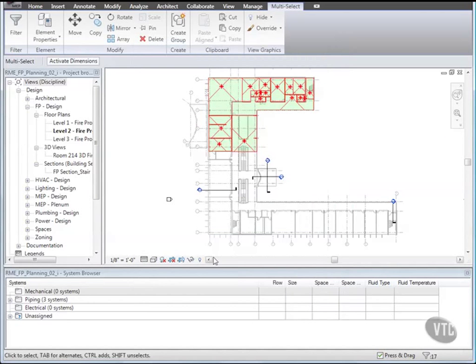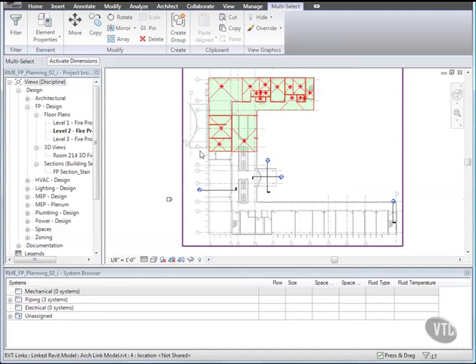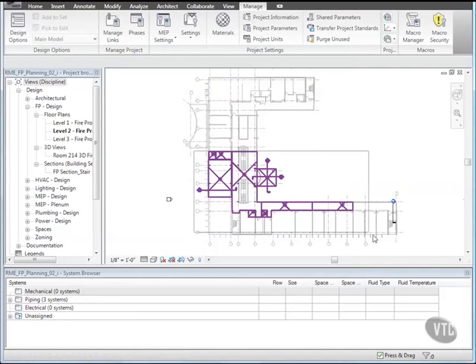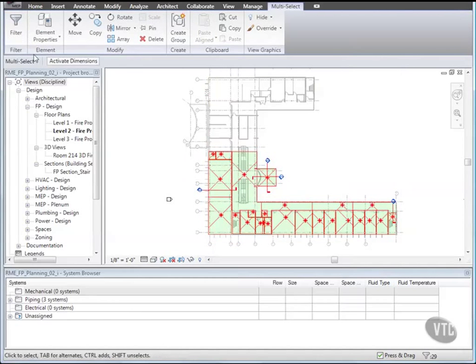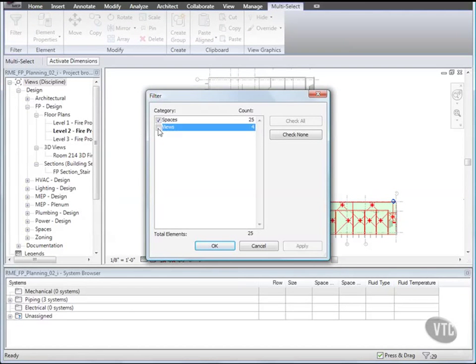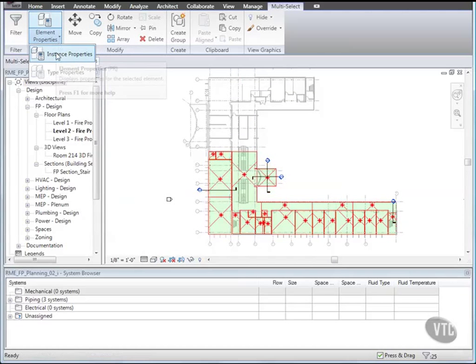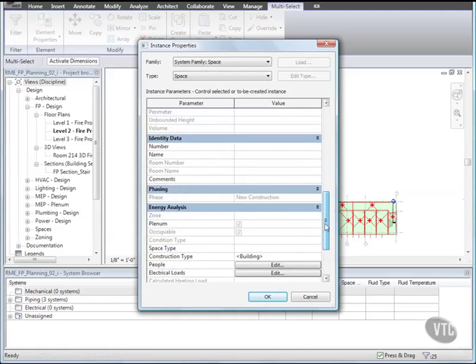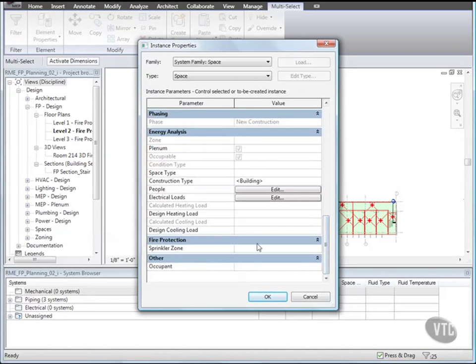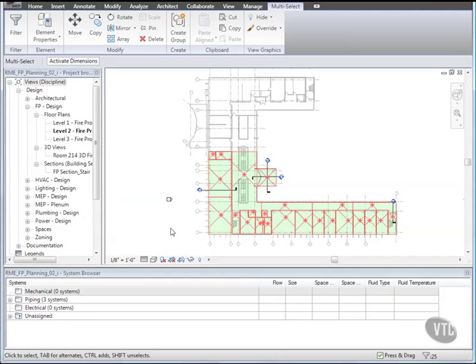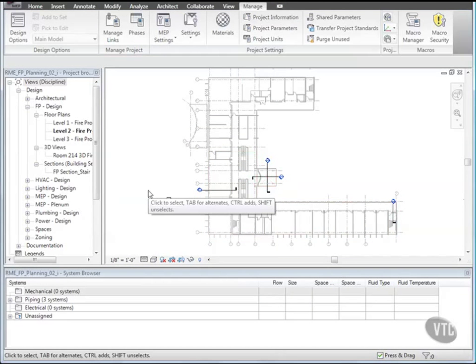Using the same method, draw a selection window around the lower half of the building. Then click Filter and make sure that only spaces are selected. Then from the Element Properties dropdown, select Instance Properties, and scroll down to under Fire Protection in the Instance Properties dialog and enter Zone 2 for Sprinkler Zone. Click OK and then clear the selection. Now all the spaces in the top portion of the plan are assigned to Zone 1 and the spaces in the bottom portion are assigned to Zone 2.